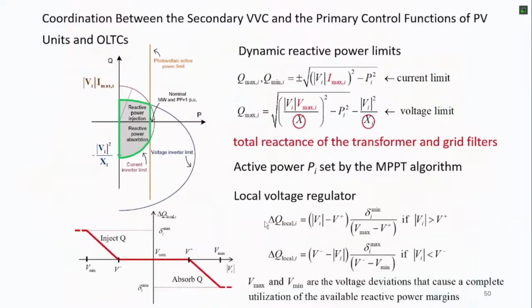And in general, for the local voltage regulator, at least in Italy there is a regulation of this type. The local regulator does nothing if the voltage is near the rated value, on the x-axis. So if it is between these two points, V plus and V minus, the local regulator does not do anything. If the voltage is lower than V minus, it injects reactive power with some droop control. And if the voltage is above V plus in the bus, it absorbs reactive power with a droop control.